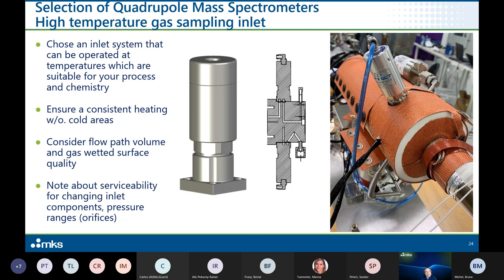Right, and another development that we are doing right now is having inlet systems at elevated temperatures. Today we are covering temperature ranges up to 120 degrees, and we have seen a number of processes where this is not efficient. There are new chemistries coming, especially from ALD, atomic layer deposition processes, or atomic etching processes, where higher temperatures are required. And therefore we have developed a new system. It's basically the same concept as the dual pass system.